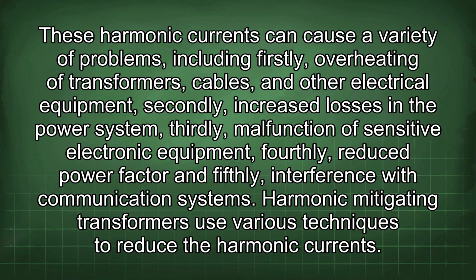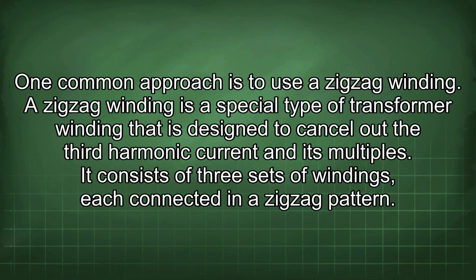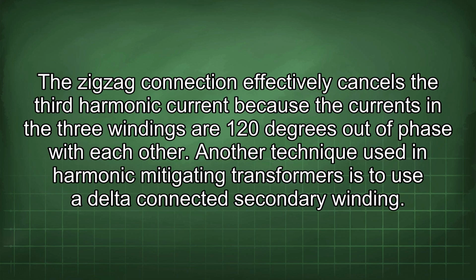Harmonic mitigating transformers use various techniques to reduce the harmonic currents. One common approach is to use a zigzag winding. A zigzag winding is a special type of transformer winding that is designed to cancel out the third harmonic current and its multiples. It consists of 3 sets of windings, each connected in a zigzag pattern. The zigzag connection effectively cancels the third harmonic current because the currents in the 3 windings are 120 degrees out of phase with each other.